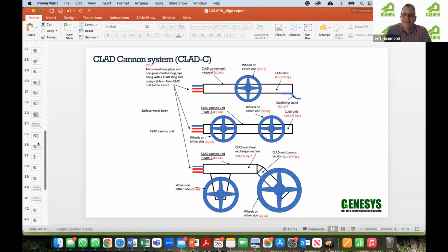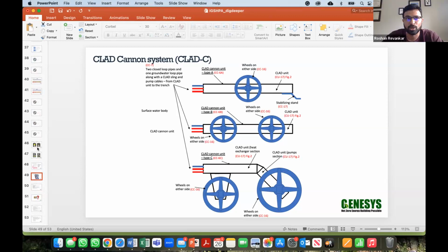Okay, very interesting. Roger asks, in the injection discharge well, is the cracking pressure adjustable for ensuring no air enters the CLAD system, depending upon static water level? What diameter sizes are available? Great question about air in the system. If you've heard of iron bacteria, that's where the problem occurs, if there's air in the system. The way the cracking pressure device is designed is to maintain pressure and no air on the open loop side as well. The cracking pressure device essentially only opens when there is enough pressure coming in from the pump discharging water into it. So there is going to be no air in the system.